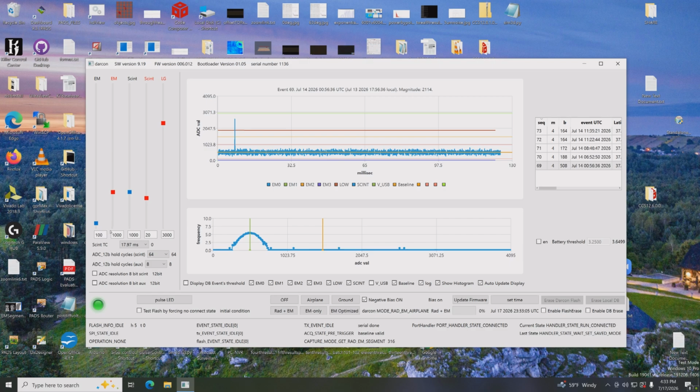But these are factory settings that I'm pointing to at the left for the thresholds for triggering. You should leave those as they're set. Do not bring them lower because it will falsely trigger on events that are not really there. But I'll explain these very quickly. EM is the threshold for showing that electromagnetic energy, such as radio frequency energy or microwaves, have occurred.